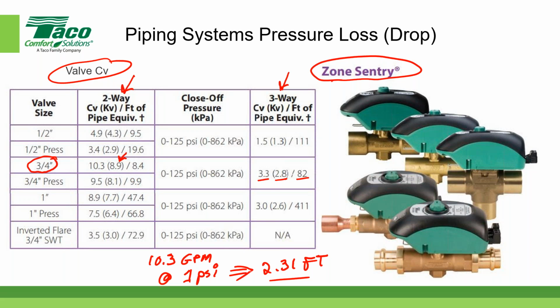Pretty cool. So we have a question about CV. Does the CV have any importance in pressure independent valves? Well, depending on the type of valve, the most common is called a PIC valve, pressure independent control valve. And generally speaking, the CV that's associated with a PIC valve is at the design characteristics when the valve is 100% open.